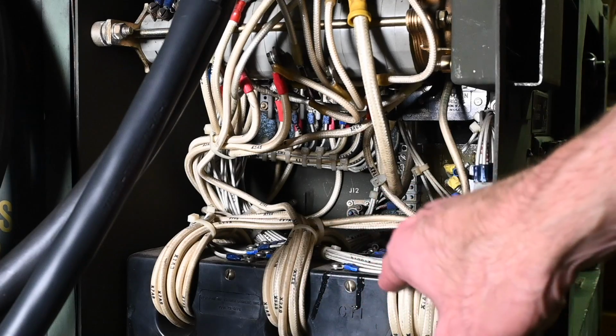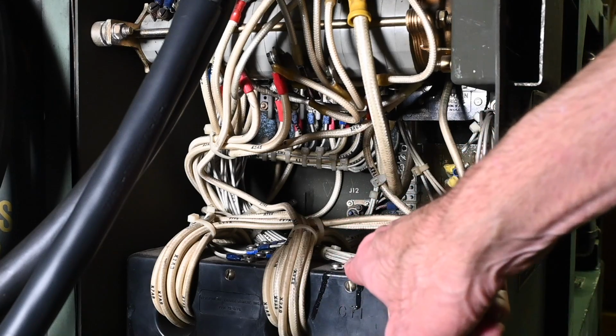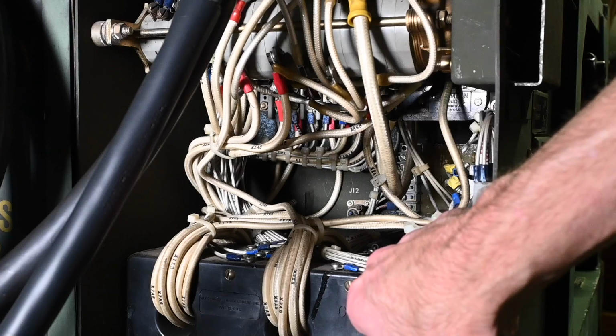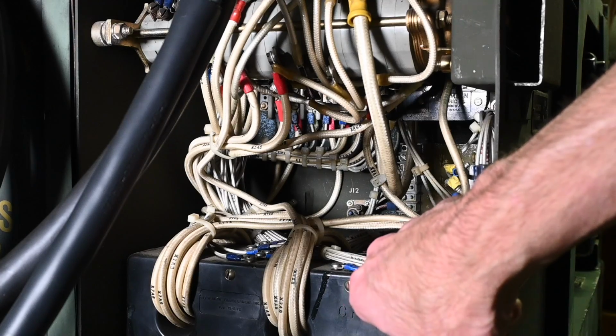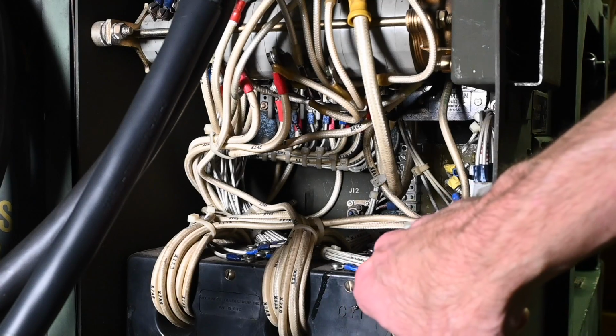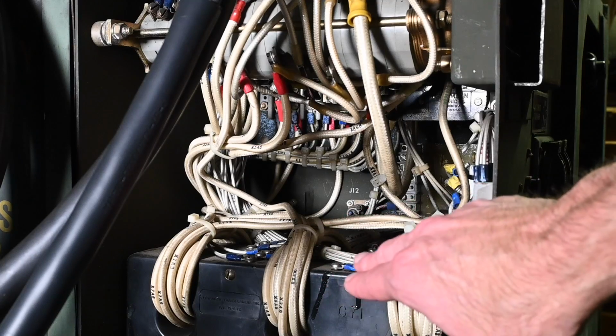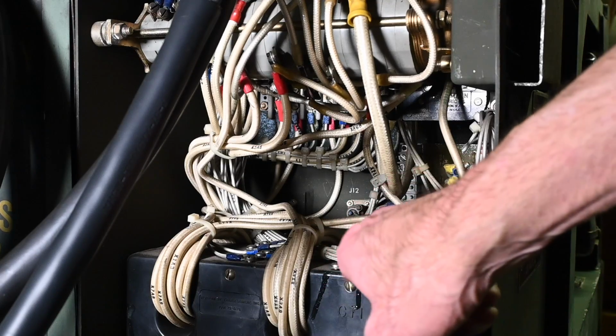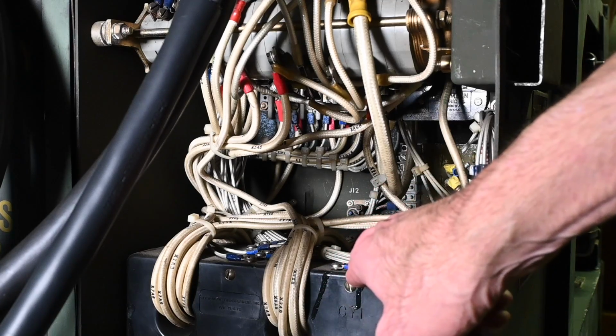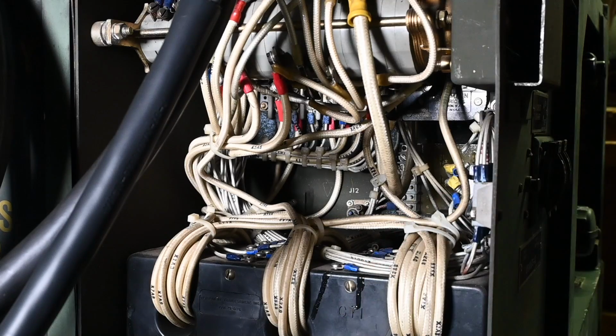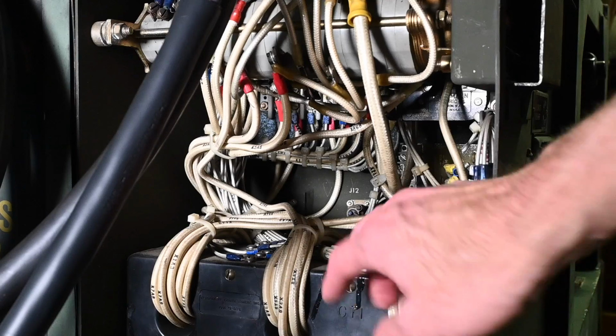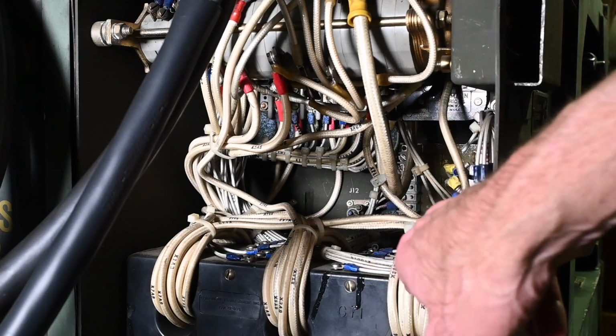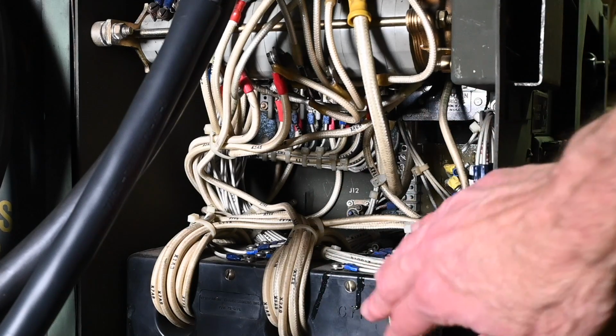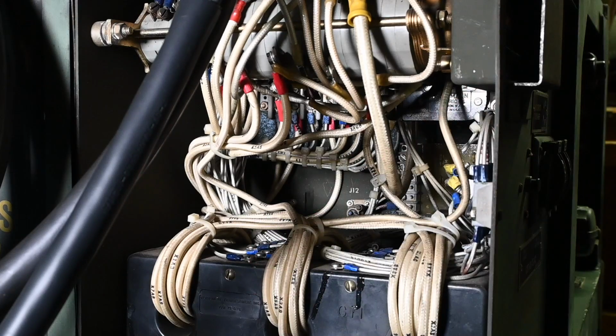Because basically this is a transformer, this is the primary winding, this is a secondary winding. There's hundreds of turns of wire typically on current transformers on that secondary, and you will have a tremendously high voltage if you have no load connected to the secondary, and it's such a high voltage that it can often arc through the insulation and damage the transformer. So if you're ever troubleshooting one of these, never disconnect one of these and then have a current that's flowing through the large wires here that are looped through these windows.